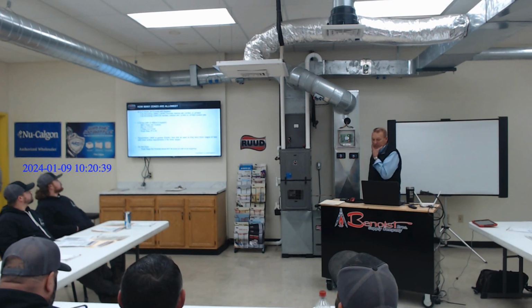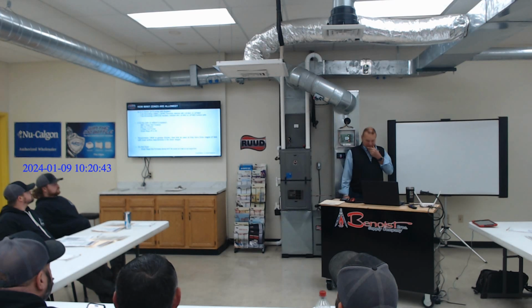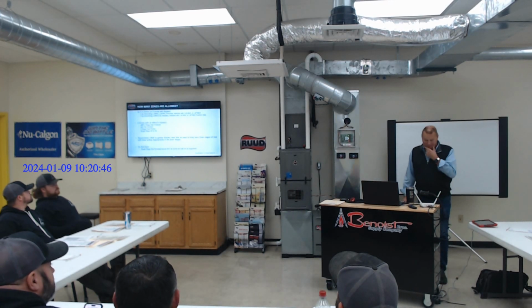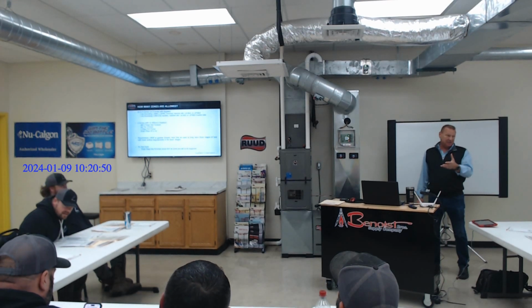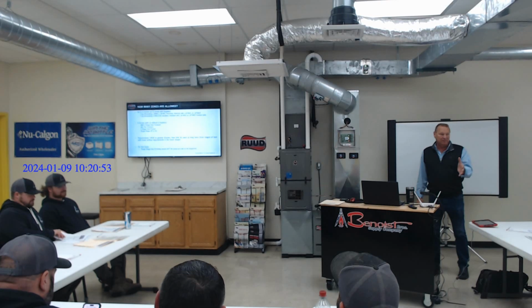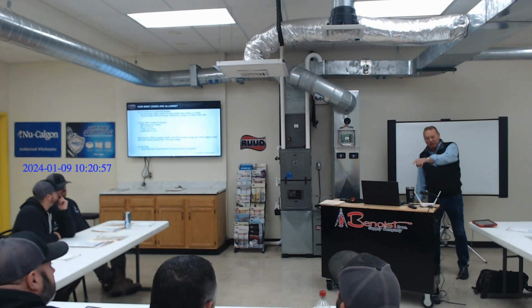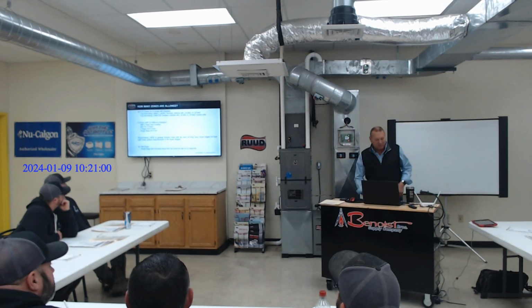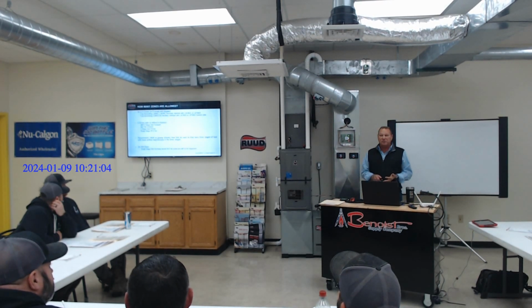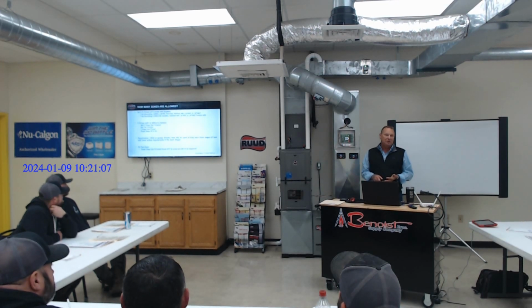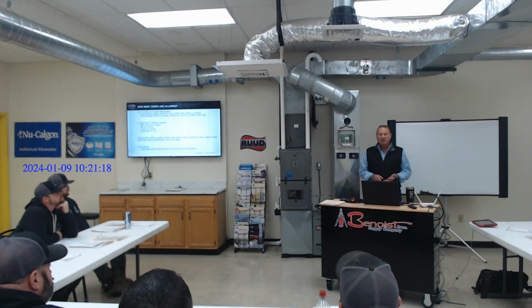On your fully modulating equipment, I can have up to 6 zones, or 5 zones with the bypass. I cannot put more than 6 zones, or 5 with a bypass, in any of my communicating zoning. Now that's the fully modulating equipment. With my mid-tier inverters today, which has changed, because my old 17 SEER I could have up to 5 zones or 6 zones, but on a 15 and 16 SEER today, I'm limited to 2 zones. I cannot put more than 2 zones in that. And here's the reason: the mid-tier product is variable speed, but it's variable speed from 45% to 75%, and it snaps into 100%, which is another training day of how that works.